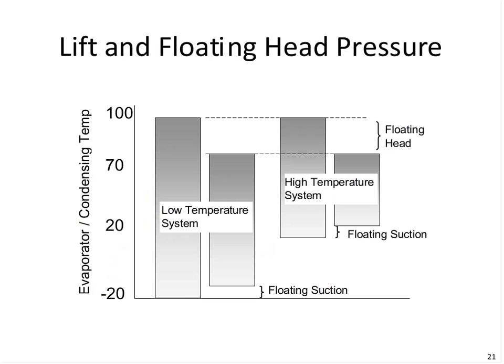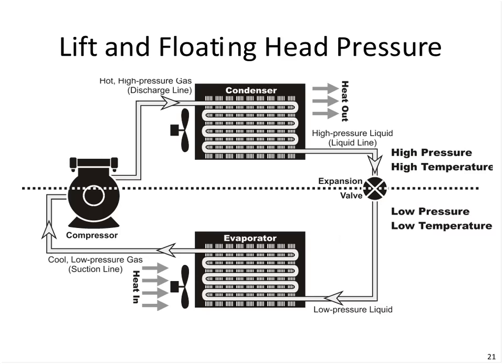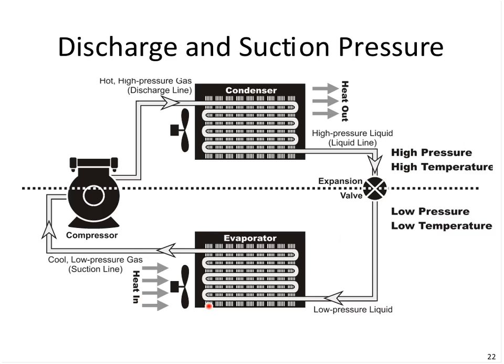So back to our chart here. We've just been looking at the floating head pressure. Let's take a second to look at floating suction pressure on the other end of the system. So what we're saying here is, how cold does this evaporator need to go? And generally, that temperature is dictated by the product or the process that we're running.